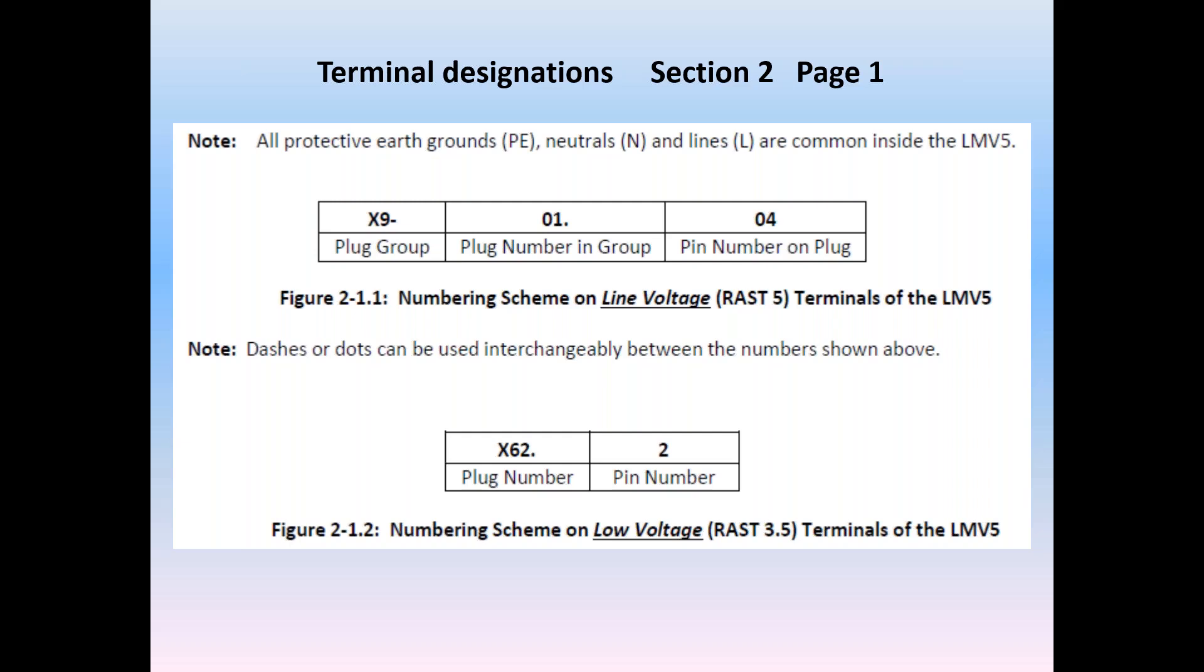Section 2 wiring should be worked along with Section 3 parameters to determine the functions of many of the terminals. Larger white terminals on top of the LMV-5 are high voltage, line voltage connections. These terminal designations have three parts, not unlike somebody's social security number. They designate the plug group, the plug number, and finally the PIN.